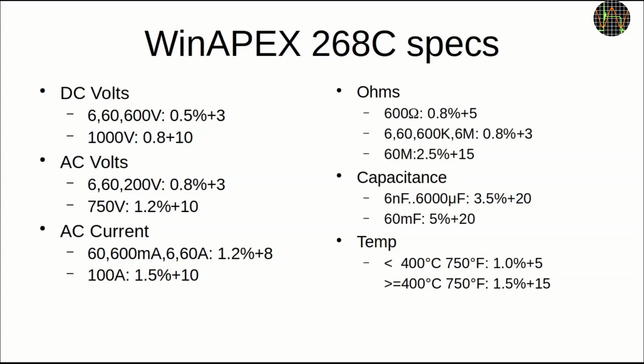The specs of the meter. It's 6000 counts and the accuracy specs are okay, but similar to many meters these days. The reason why you may want the 268C specifically is the sensitive AC amps mode. Of note, there are 3 different models of this clamp meter, which is why the 268C has buttons that don't seem to do anything. The 268B model has the most functions in that it can do both AC and DC amps, and with higher currents than 100 amps, and it also has frequency measurement. But only the 268C model has the sensitive 60 milliamps AC amps range needed for leakage tests.